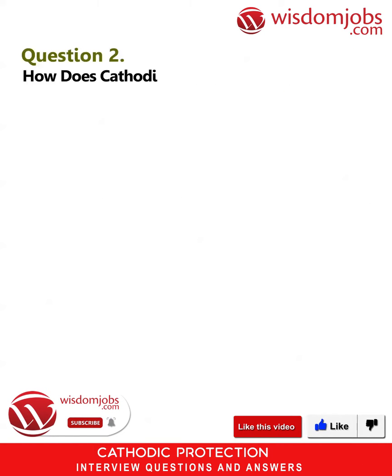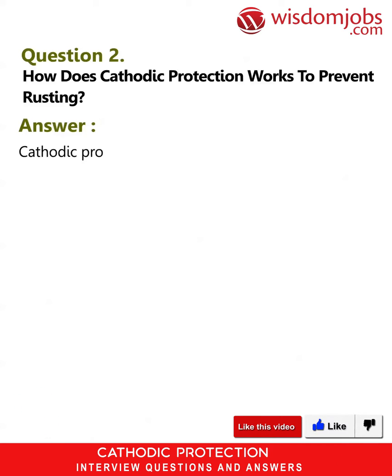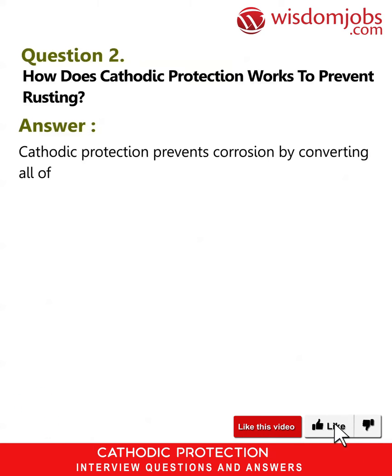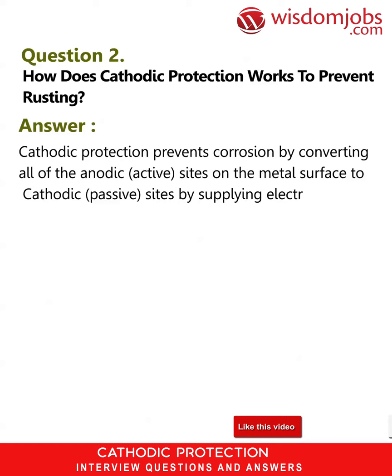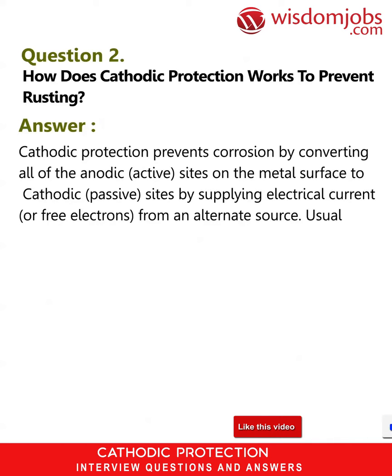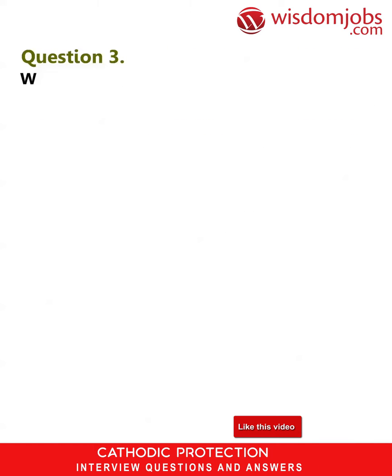Question 2: How does cathodic protection work to prevent rusting? Answer: Cathodic protection prevents corrosion by converting all of the anodic (active) sites on the metal surface to cathodic (passive) sites by supplying electrical current or free electrons from an alternate source. Usually this takes the form of galvanic anodes, which are more active than steel.